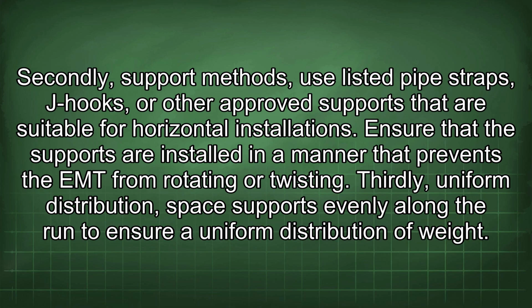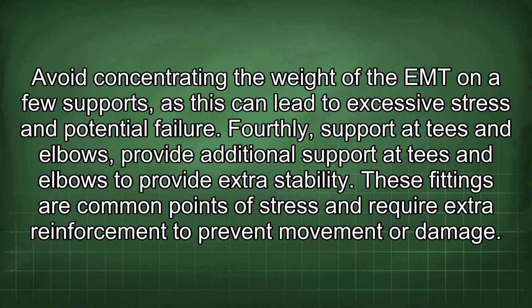Thirdly, uniform distribution. Space supports evenly along the run to ensure a uniform distribution of weight. Avoid concentrating the weight of the EMT on a few supports, as this can lead to excessive stress and potential failure. Fourthly, support at T's and elbows. Provide additional support at T's and elbows to provide extra stability. These fittings are common points of stress and require extra reinforcement to prevent movement or damage.